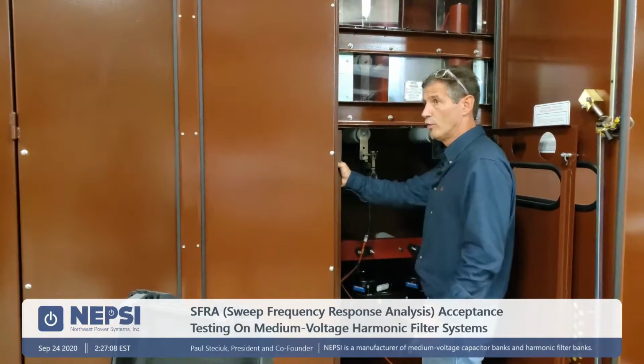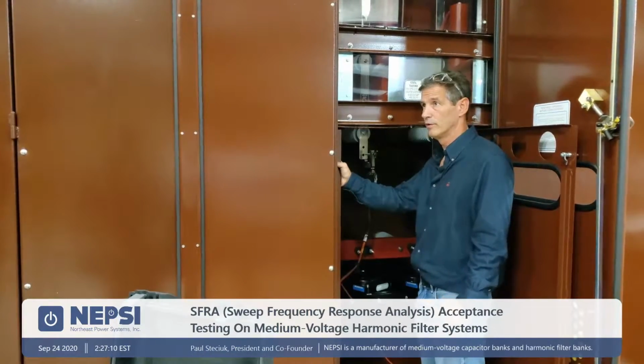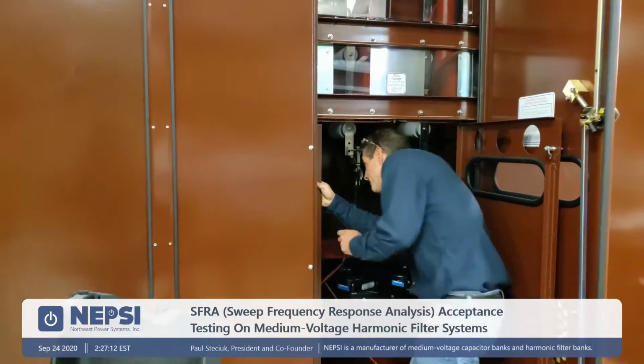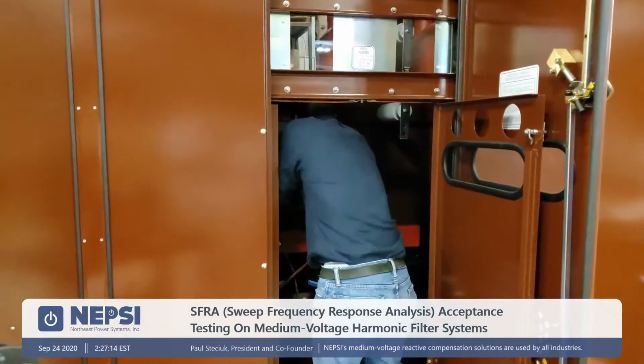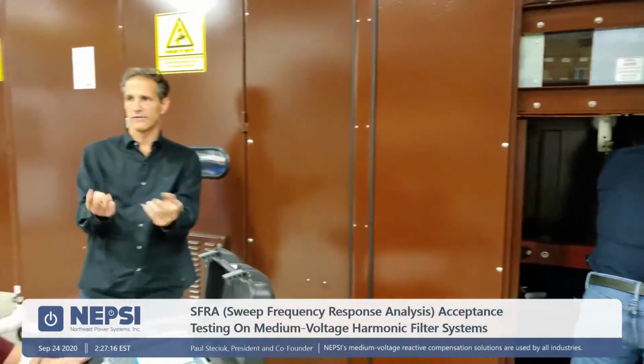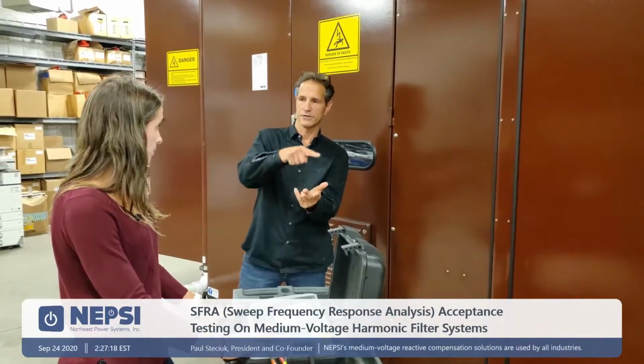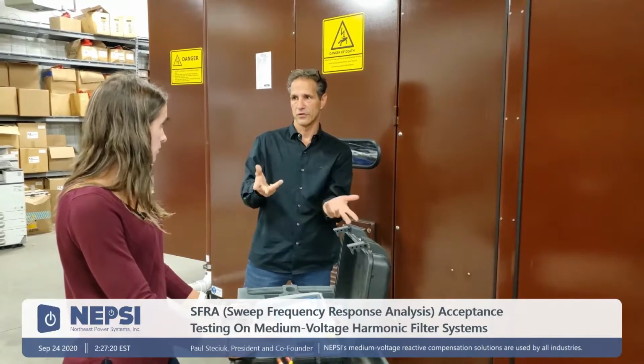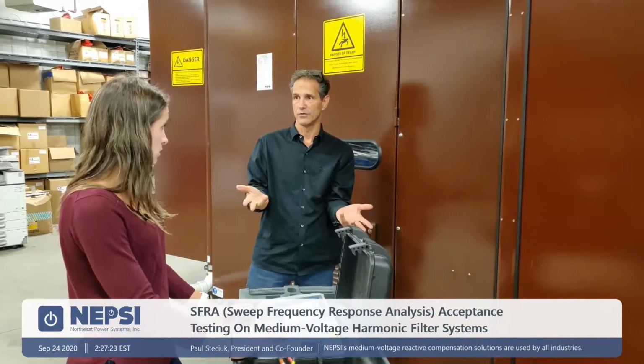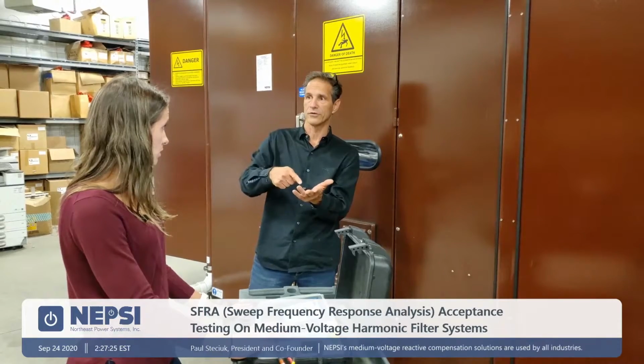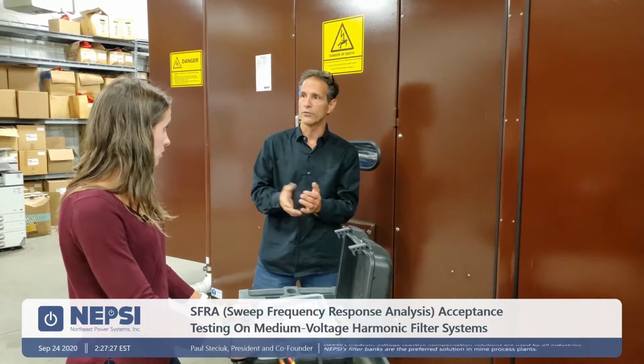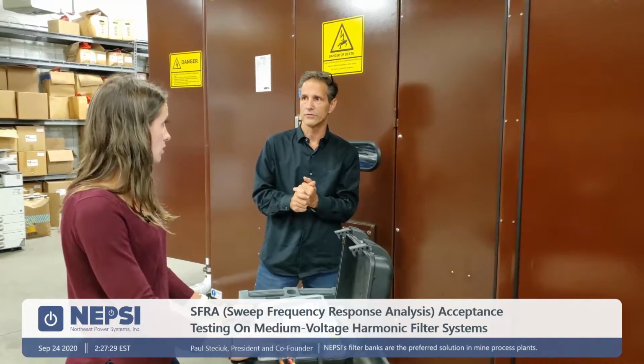We will overlay the three tests onto one another. All right, so you do A to B, B to C, C to A. You have three tests. Yep. And you're testing phase to phase rather than phase to neutral, so you have double the impedance. Correct. Right, so when you do your report, we end up having to cut it in half. Is that what we do? Yep. Okay.